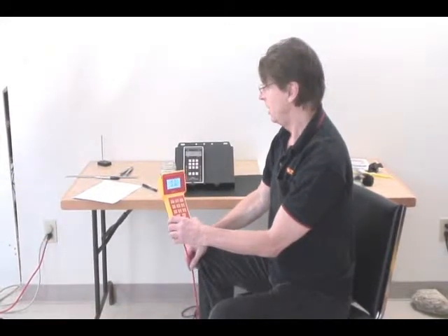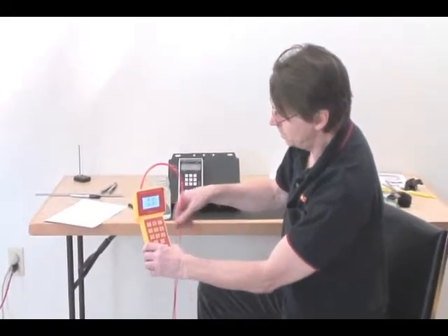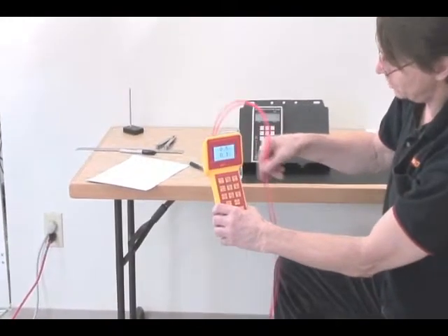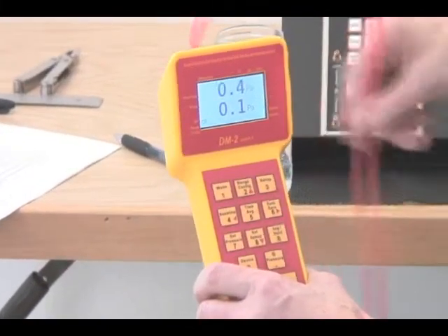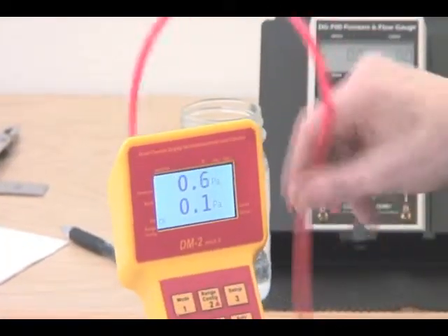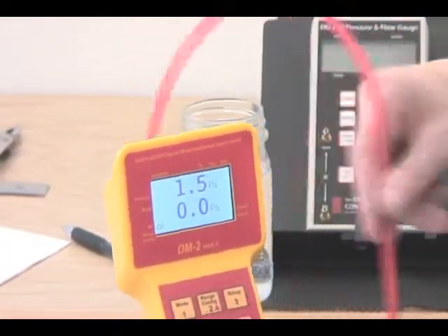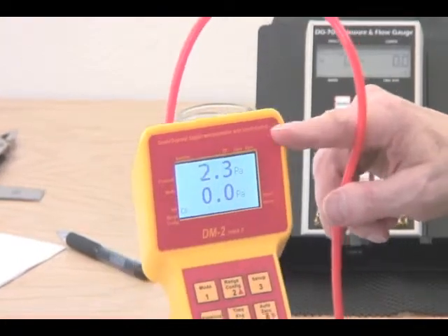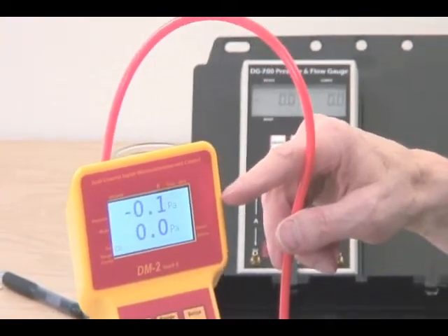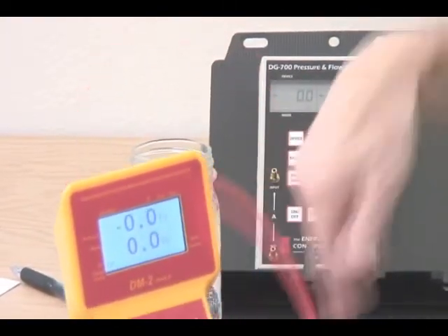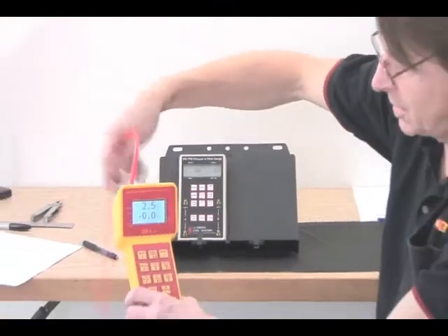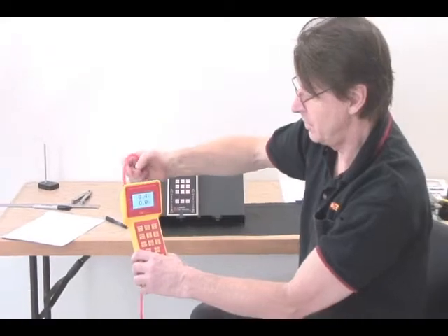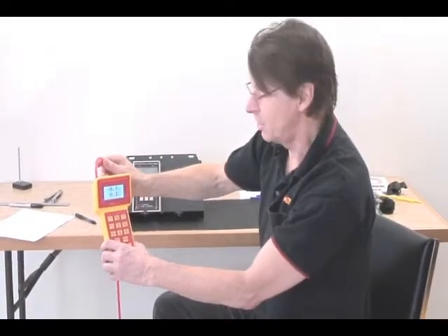The first one is the moving tube problem. So all we do is we take this tube and we move it around, and you'll notice on the display here that it's changing quite a bit. It's changing as much as 2 pascals just by moving the tube around. And this is something that might occur if your tube was outside and was elevated and the wind was actually moving your tube around, or the tube was, say, somehow unsupported. You definitely don't want this kind of thing, so your tube must be secure.